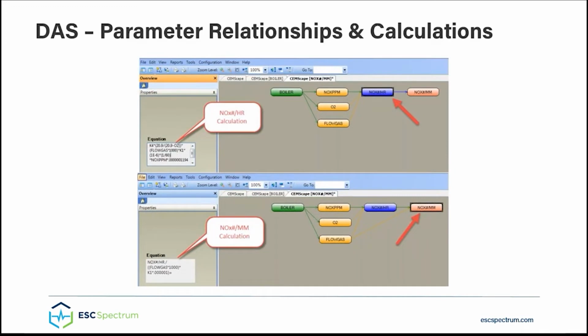So here we've selected NOx pounds per hour and extracted it and its related parameters into their own view. On the left side, we can see the equation used to calculate the NOx pounds per hour value. Looking at the equation, note that it's dependent on the O2, NOx ppm, and flow gas parameters. And looking at the graphic display, you can see the dependency lines feeding into it from these parameters. Similarly, in the bottom example, we've highlighted the NOx pounds per million BTU parameter, and we can see its equation and the parameters that feed into its calculation. This feature is very useful for understanding your DAS, troubleshooting data issues, and helps when adding new monitoring parameters to the DAS.